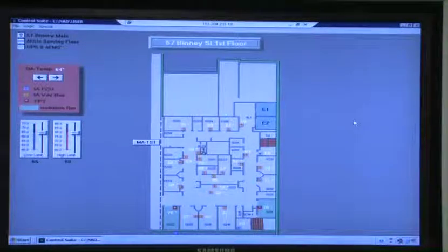So if that box is breached in any way by doors open, then you're going to lose pressure. You don't need alarming. That's why we did it. That helps us because of all the things we had up there at 600 and 614. I'm going to go back and get that, guys. I think that's going to be on my list for this year, to attack that one again and see how I can modify that and get that nuisance alarm stopping. It is a nuisance.